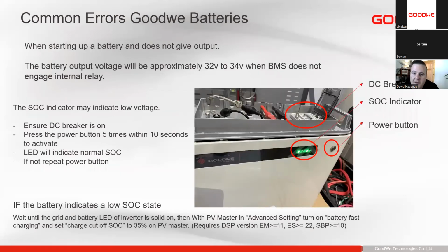So when we start up a battery, the indicator might indicate low battery or anything like that. It's not really giving output. We measure with a multimeter, and we might see approximately 32 to 34 volts. And that means the battery hasn't engaged its internal relay. So typically we can then force it to go on. We can ensure that the DC breaker is on, it's connected to the inverter. We press the power button 5 times within 10 seconds. So that power button will press 1, 2, 3, 4, 5.